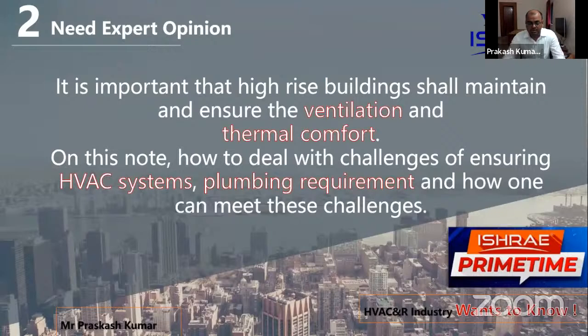Moving ahead, all supply chilled water pipes should have at least a motorized valve along with an orifice plate to ensure pressure loss is uniform across all AHUs. It may happen that one AHU has more pressure loss and another has less, so water will take the path of least resistance — to avoid that, we do this. In the chilled water piping network, we must also ensure provision of an expansion tank, which can be pressurized or normal, connected at the top point of the circuit and placed at the roof. I personally prefer a pressurized expansion tank because it's foolproof.